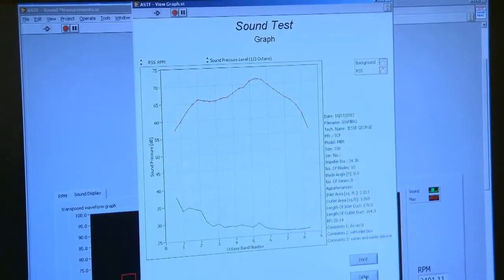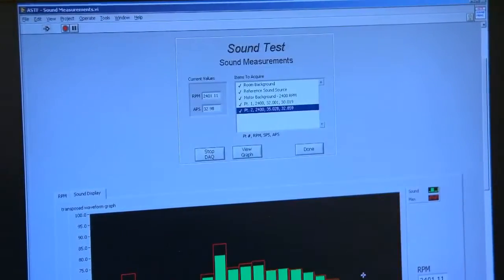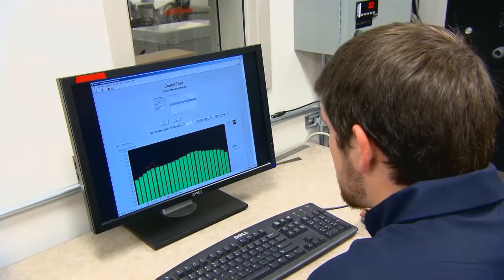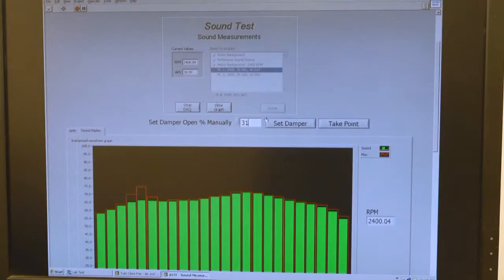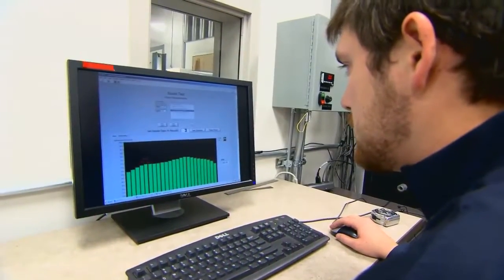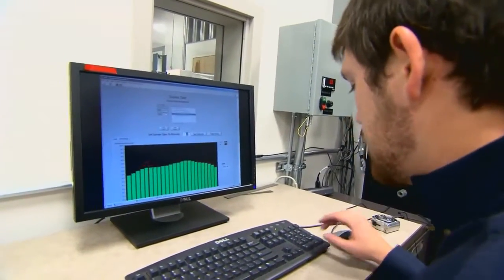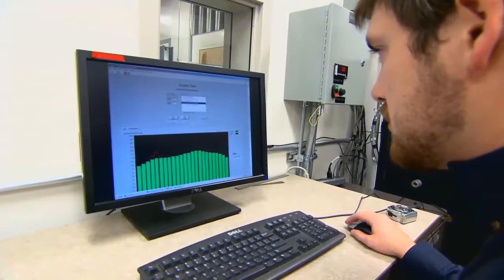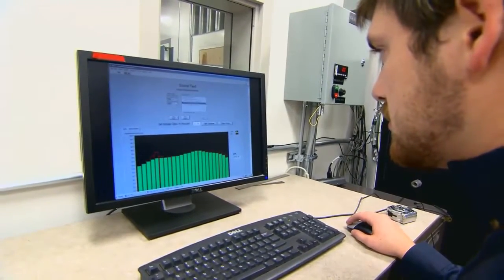At the end of the day, when we look at the sound spectrum in our sound graph tool, we want to make sure that the levels are low. We can do synthesis of the frequencies to simulate the response of a human ear — that is called A-weighting. So the key number that we look for is the A-weighted sound spectra, which will generally tell us the idea of the sound quality of a fan.